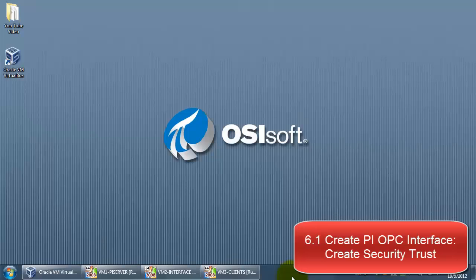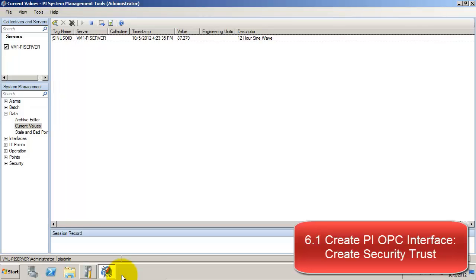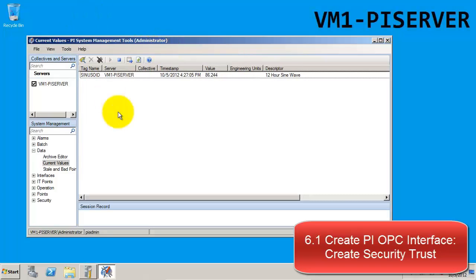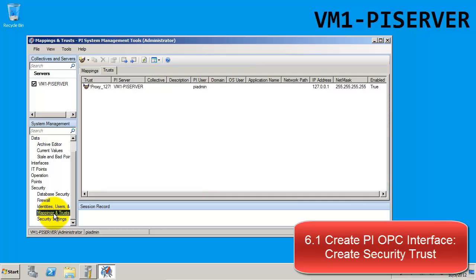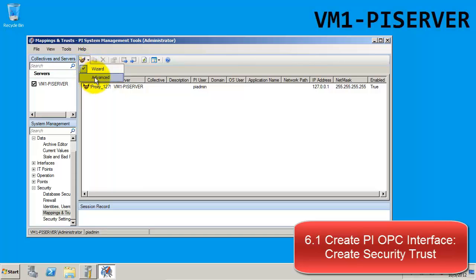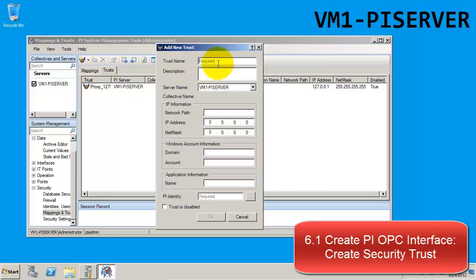To do this, we'll return to the PI server node and use System Management Tools, or SMT. From here, navigate to the Security tab, then Mappings and Trusts. We have both a Mappings tab and a Trusts tab. Since we're creating trusts, we'll stay on the Trusts tab. We'll create a series of trusts using the icon up here, selecting Advanced Settings. When configuring trusts, set them up using the fully qualified domain name, the short name or computer name, and IP address. We'll start with the fully qualified domain name.